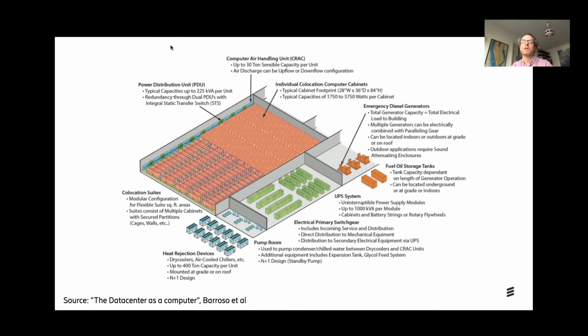And in case of power outage — and of course you always have power outages — you need a set of batteries, a UPS, uninterruptible power supply modules. But those UPS units cannot run forever, and you need one UPS per power line, so there's replication in the UPS system. Then you need emergency diesel generators that can power the UPS, and of course the emergency diesel generator also has to be redundant. So everything here is built to at least sustain a wide number of faults without causing a failure.